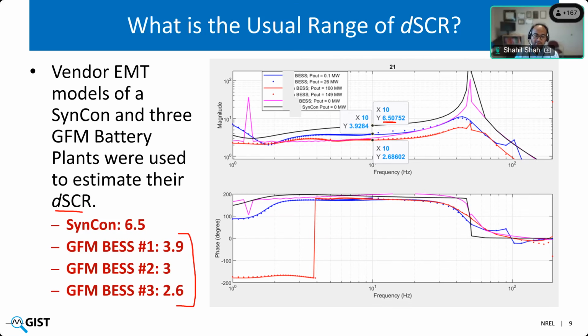I can add my thought on this, and then Deepak can add. So it's really about selecting a fast time scale, because we don't want to go into the steady state realm where even with grid following controls, you can have droop gains and provide primary frequency response or something similar for voltage response. We wanted to look at fast time scales. That is one reason to convert that into 4 to 40 hertz. You can push the 4 hertz to even a little lower value like 1 hertz.